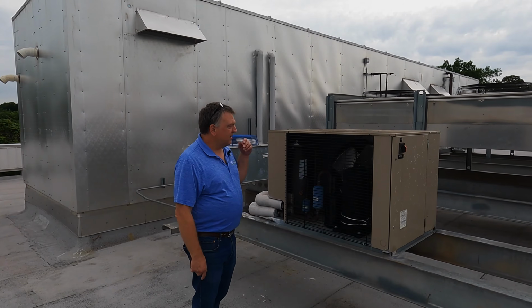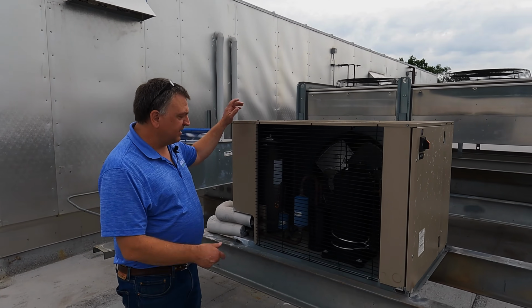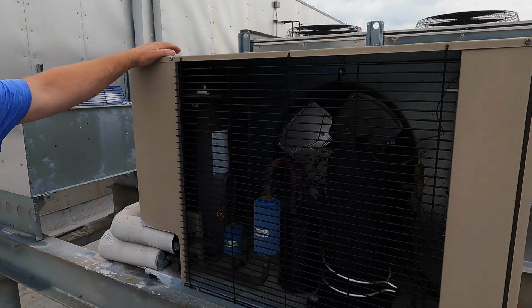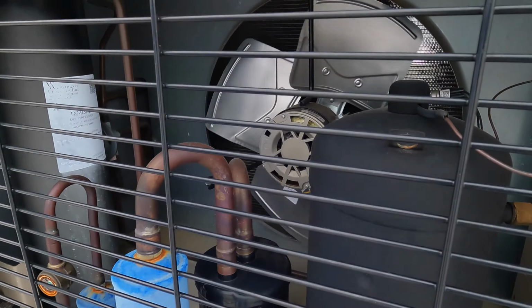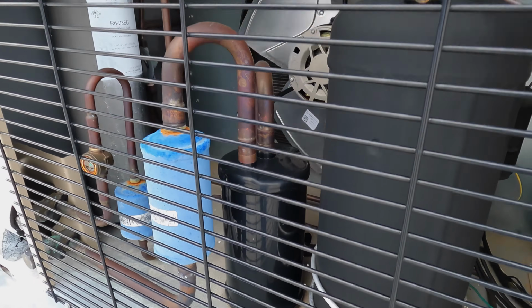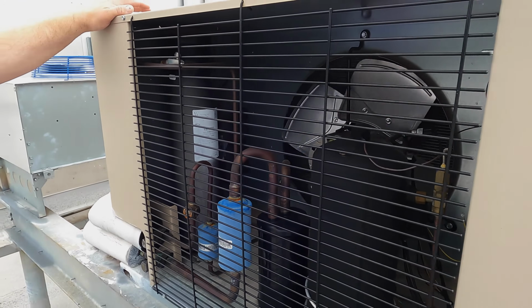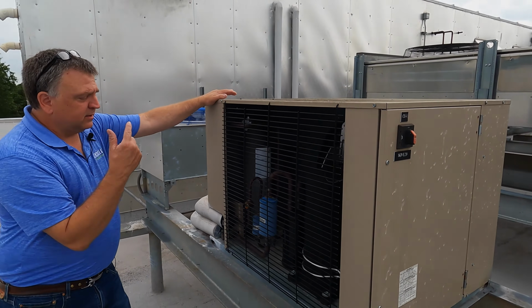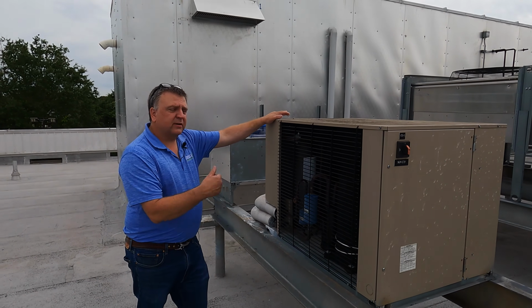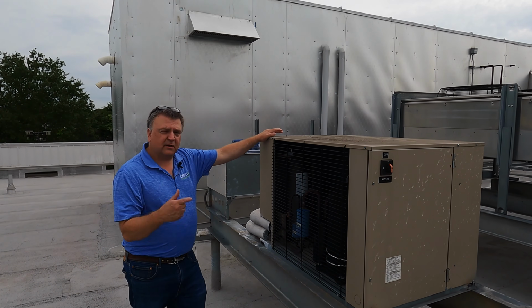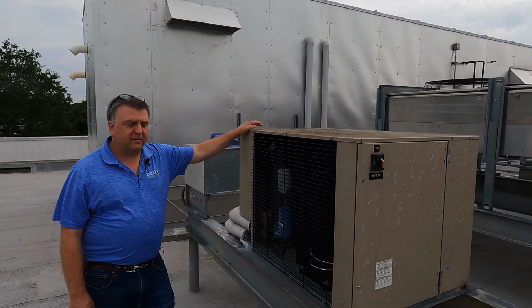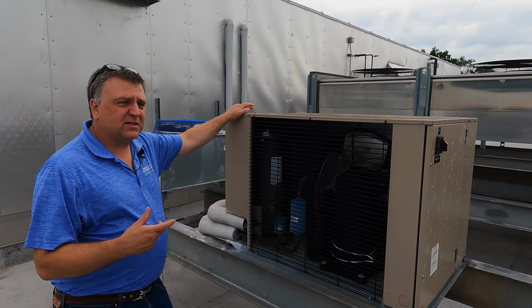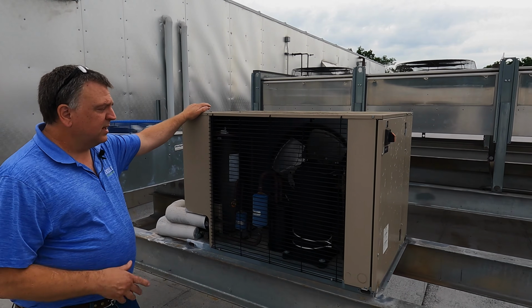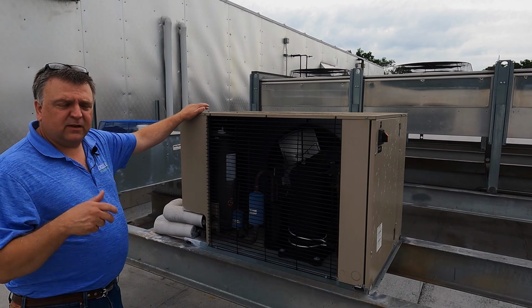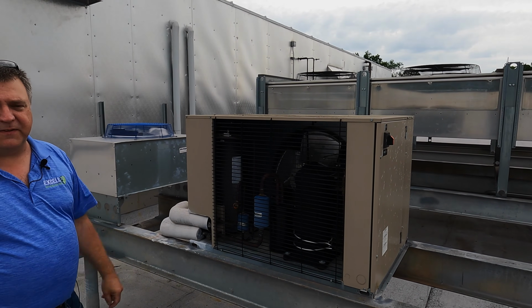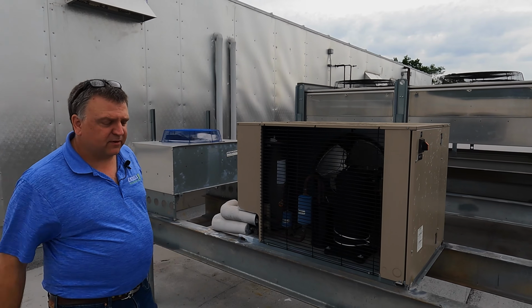So this is our auxiliary condenser. And as you can see, it's just a basic refrigeration condenser with a scroll compressor. So when that liquid line solenoid inside energizes, it's going to create higher pressure, cause the low pressure switch to close, and bring the compressor contactor on. It's going to start cooling that CO2 down for us. Like I said, this is small scale. All it's supposed to do is keep the CO2 from exceeding 650 pounds. We try to keep it around 500 pounds.